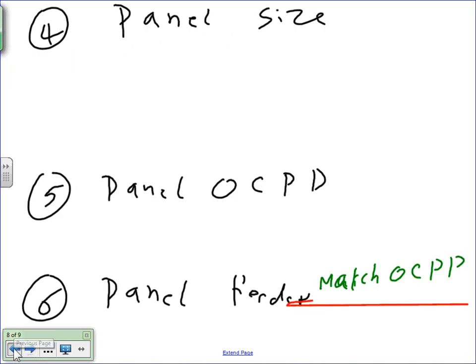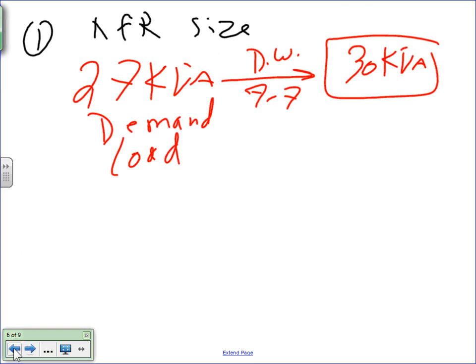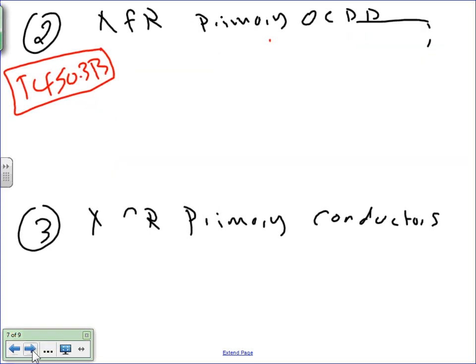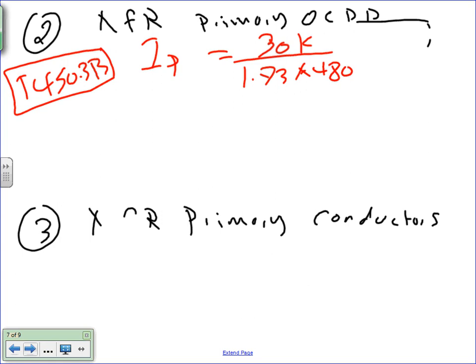All right, so we found number one, the size. Number one is the size. Let's go to number two. I need the primary overcurrent protection device. The primary overcurrent protection device, number two, guys, is basically I primary equals 30K divided by 1.73 times the primary voltage. The primary voltage is 480, right, Chris? 480. You're going to end up with 36 amps. And you can find it actually from the table that you guys have. It will tell you the full load amps from these tables, 36 amps.